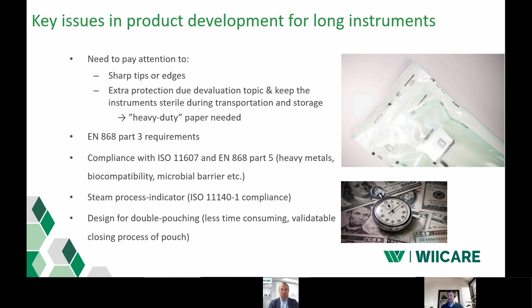Processing in steam will set certain requirements for the paper, like fulfilling the standard EN 868 Part 3, but also requirements for the whole package for complying with ISO 11607 and the standards like EN 868 Part 5. Furthermore, it would be important to have a steam process indicator printed on the pouch outside of the packing area. As we have a wide spectrum of medical grade papers tested in-house and experience how they work, we decided to proceed with the most promising one, a grade which was offering really good properties in all aspects.